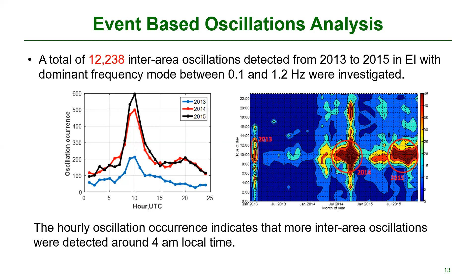There's a need to know where, who, and what is causing the oscillation. If you find where, usually a generation station has multiple machines, so you'd like to know which one. Even knowing which one, you may not be able to interfere easily, because if you find out it's a nuclear unit, you're not going to shut it down. You want to know if it's the electrical system, excitation system, or mechanical system causing it, and you may need to make an adjustment. I'm not going to shut a nuclear plant down easily, because that's not what it's designed to do.